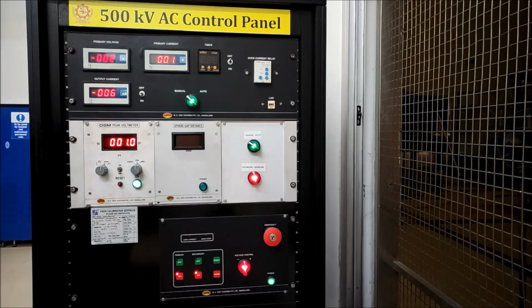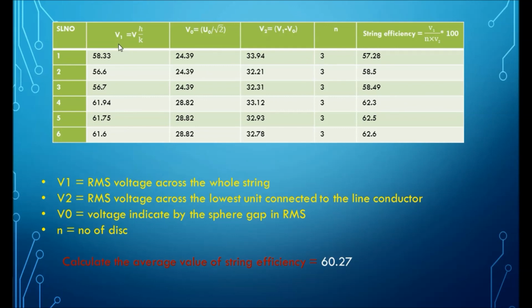I have taken 2 readings. First the reading for the 1 cm distance of the sphere, then again set the distance to 1.2 cm, then take the readings. I have calculated, you can see, this is V1, the voltage across the whole string in RMS value, and this is the sphere gap voltage, and this is the voltage across the lowest unit connected to the line conductor, meaning near the high voltage conductor, and the number of discs is 3. Then you can finally calculate the string efficiency, and this is the average value of string efficiency.